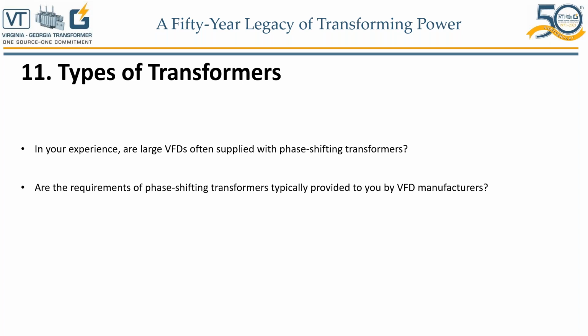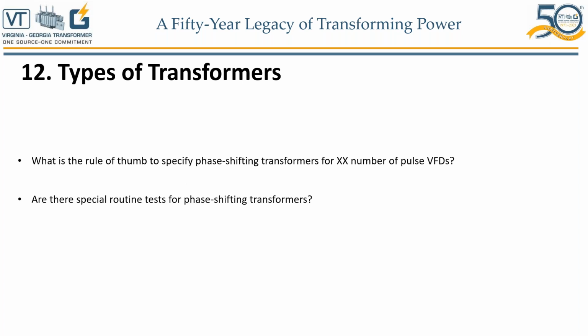Second question is, are the requirements of phase shifting transformers typically provided to you by the VFD manufacturers? No, the requirements for phase shifting transformers are supplied to us by whoever is purchasing the transformer. So the purchaser is going to have to get together with the VFD manufacturer, define what they want the phase shifting transformer to be like, and then give us the requirement finally. We don't have to get in touch with the VFD manufacturer separately. We like to have only one spec, one requirement, coming from the transformer purchaser themselves. Going into the next.